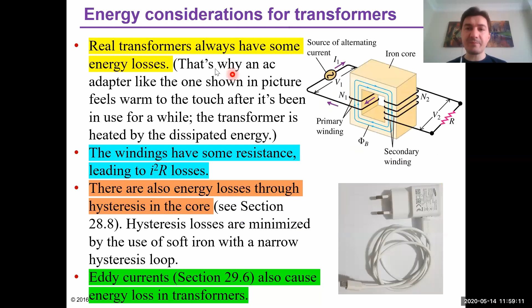So we've discussed three reasons for energy losses in transformers, and to decrease these losses we can use soft iron cores, which have a hysteresis curve with smaller coercive fields. We can also use lamination—ferromagnetic plates in the iron core of the transformer. Then we can reach efficiencies up to 90% or 99%, depending on the design. So here we have a very nice example of the transformer.